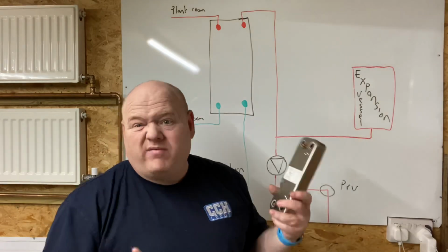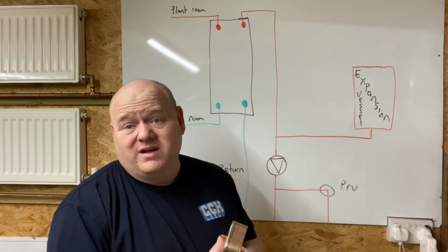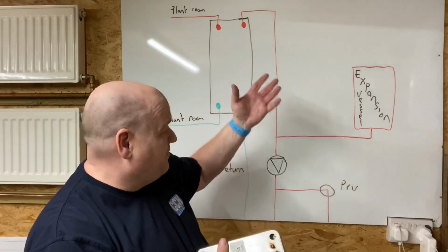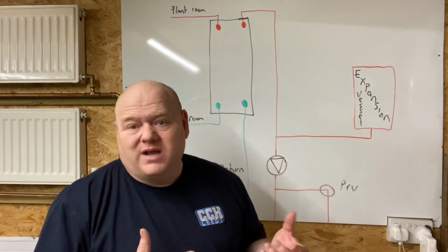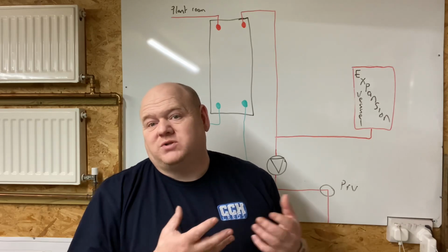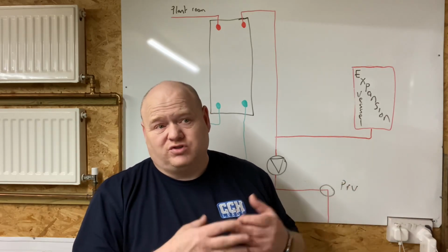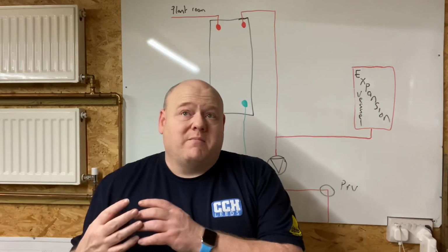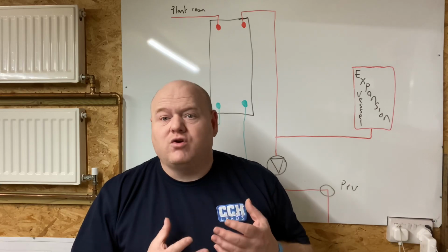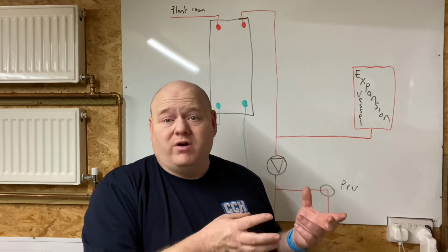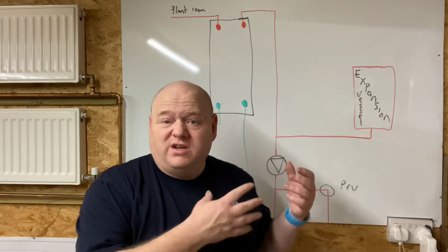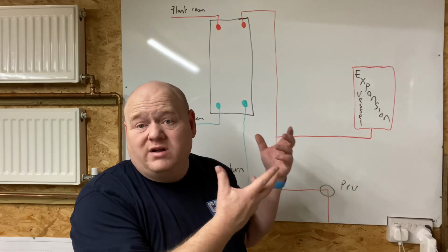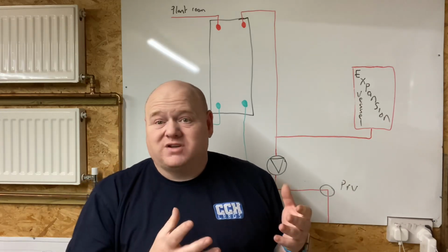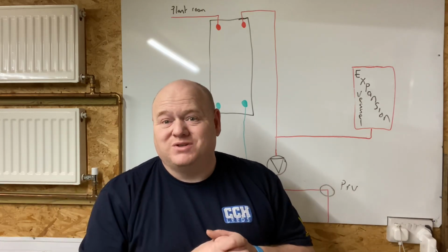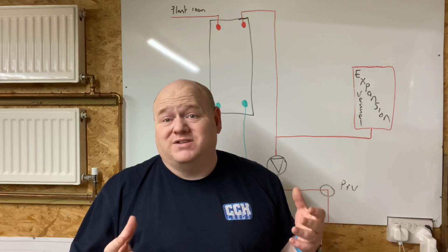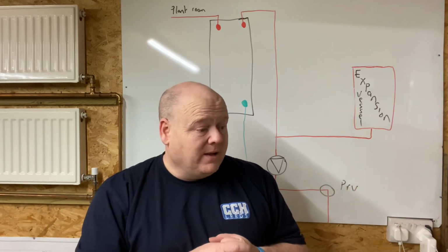Yeah, I hope I've explained this in the best way I can. The reason you'd have this type of system is that a lot of times nowadays, as David had said, they might be trying to use new technologies. They might be having biomass or solar or whatever. They might have plant rooms. A good thing would be, if you've got a big massive plant room and one of the boilers fails, they'd have backup boilers. So you're never really going to be without hot water and heating with this type of system. Obviously this is not a system that's going to be used a lot in comparison to combi boilers and things like that.